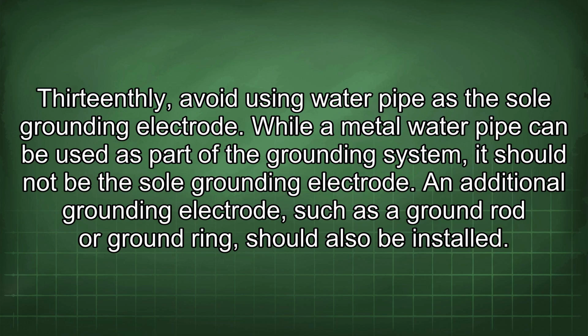13thly, avoid using water pipe as the sole grounding electrode. While a metal water pipe can be used as part of the grounding system, it should not be the sole grounding electrode. An additional grounding electrode, such as a ground rod or ground ring, should also be installed.